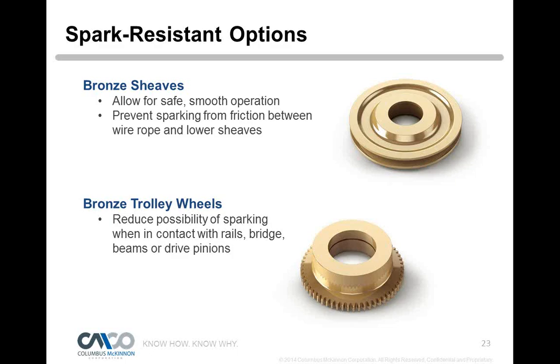So there's the difference where, hey, all I need is explosion-proof because I have a potential of vapors building up over time within my enclosure, but I really don't have any potential in my work area down below for that to happen. So that's why some people say, I know I don't need the spark resistant options and don't want to pay the extra money to do that. Would I try to talk someone out of doing that? I would mention that you could save money here, but if they say, no, I want to be ultra safe, then certainly I would go for the spark resistant options.